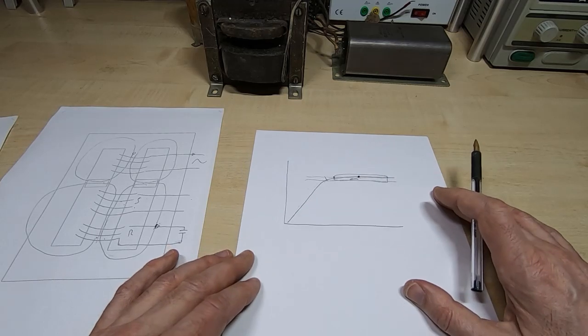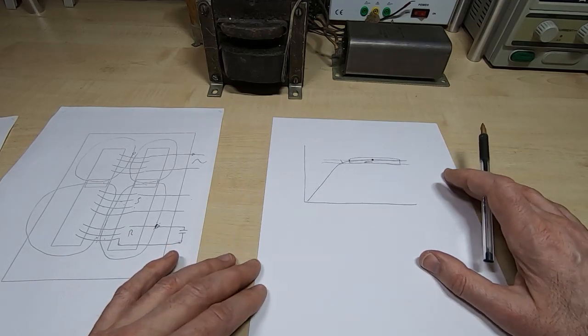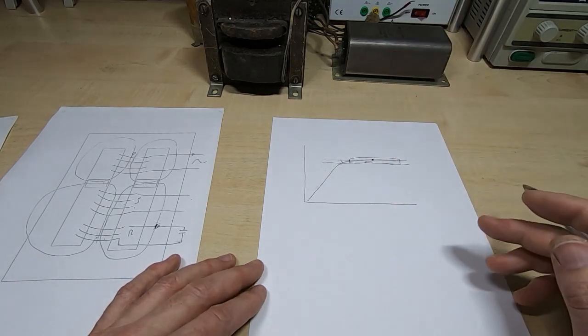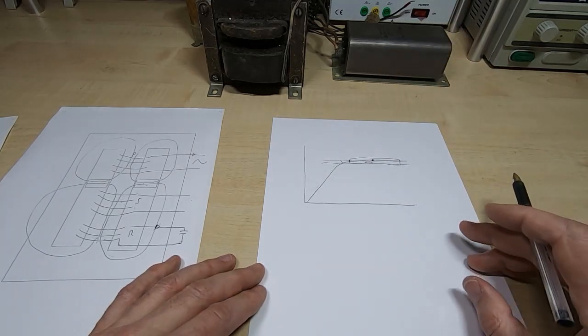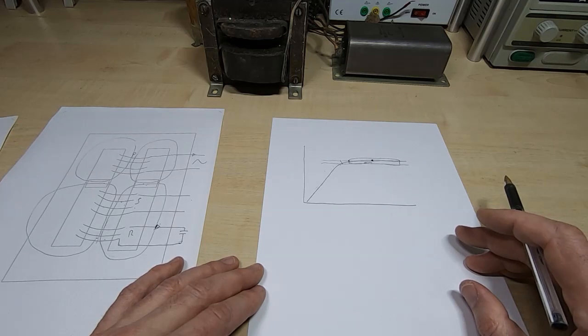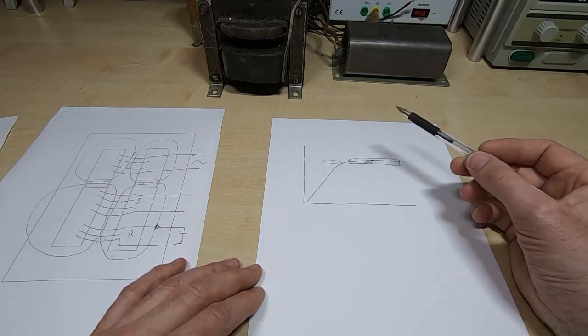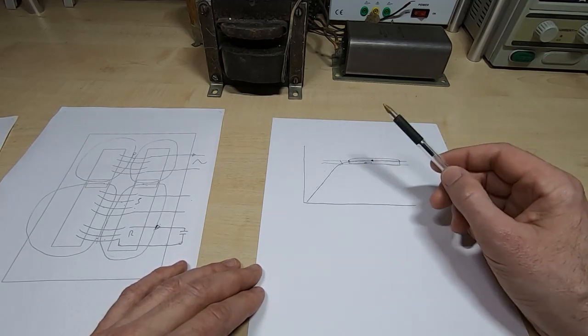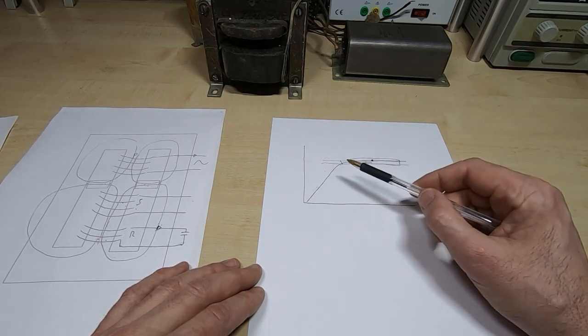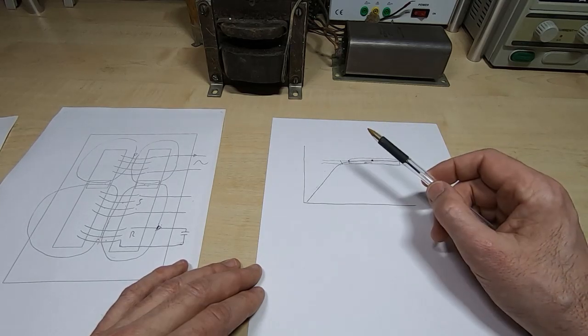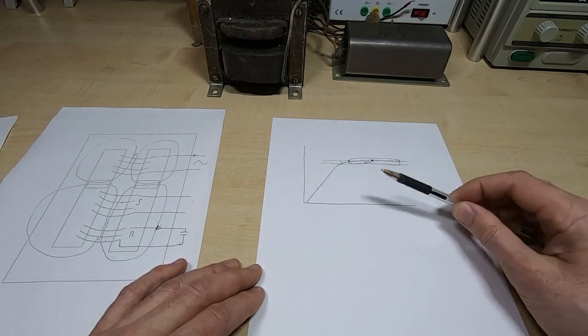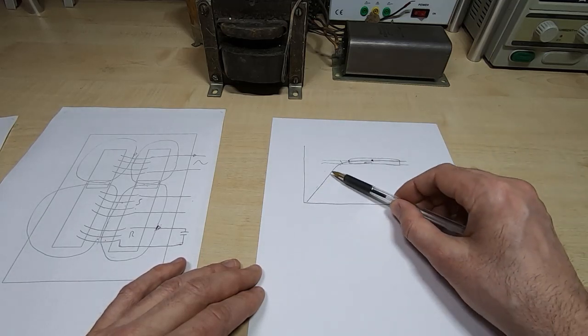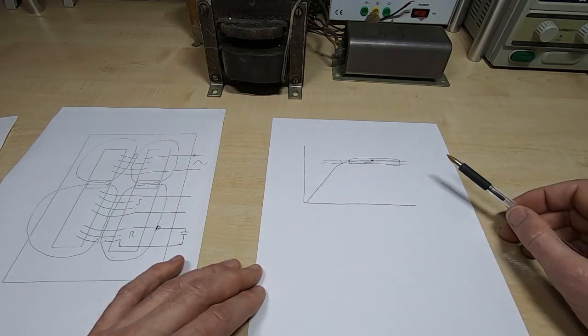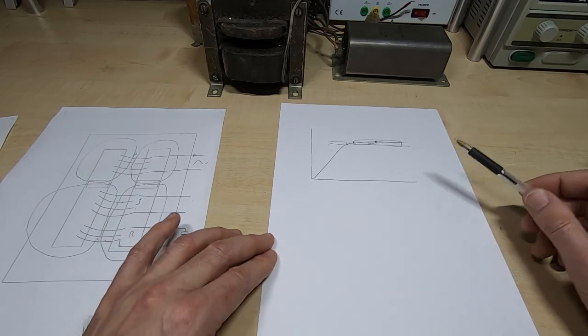So the next thing to consider with a ferroresonant transformer is the load design, and it is fairly critical to get the load design correct. If you just start to apply low AC voltage to the transformer, you'll find it will have a very high AC current. The current will suddenly start to drop once we get up into the proper operational band for the transformer.